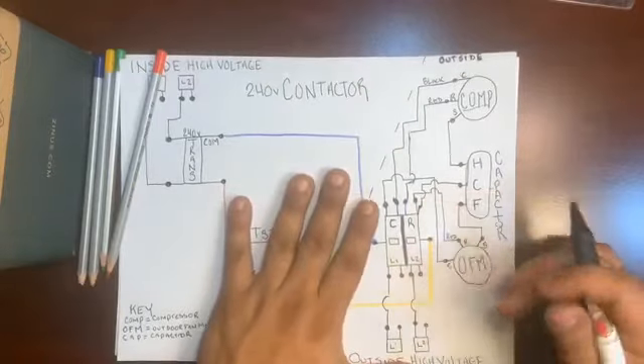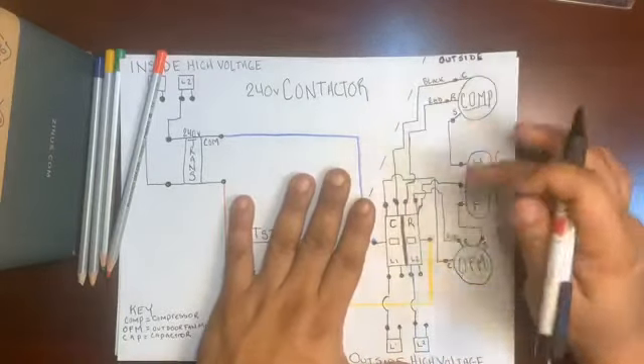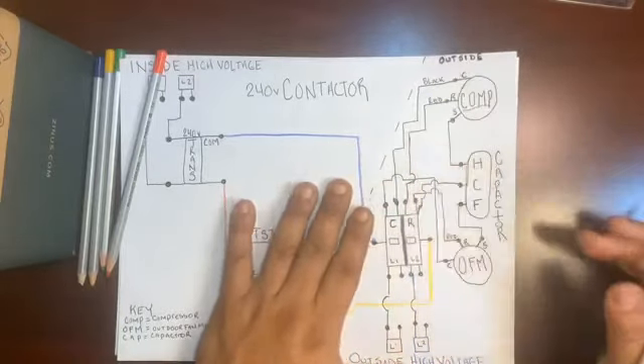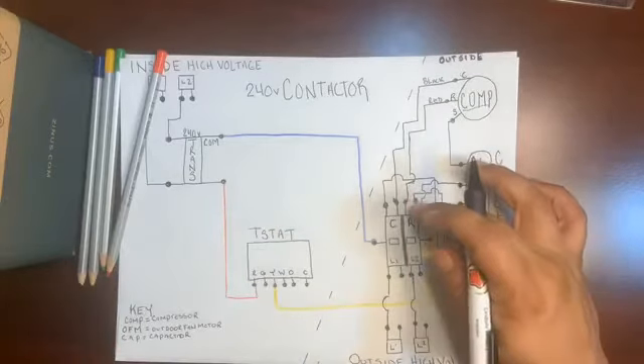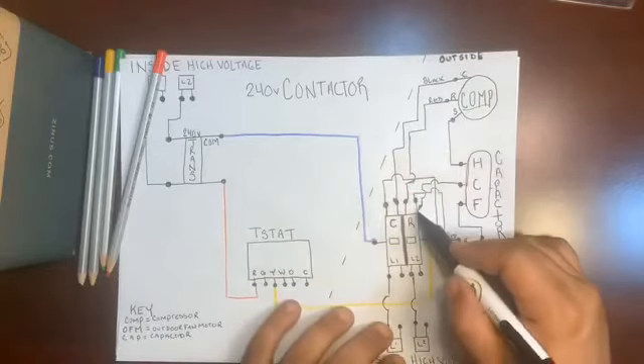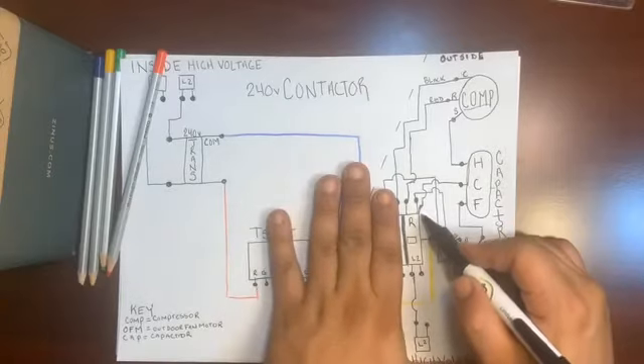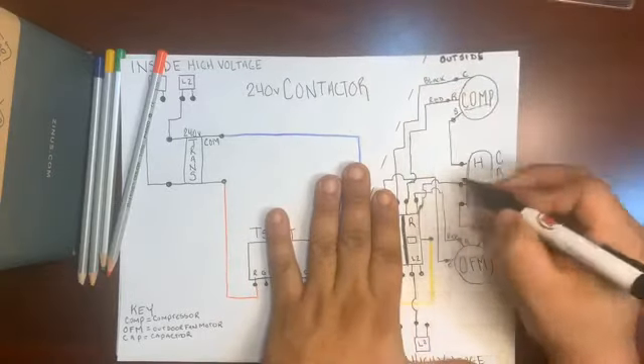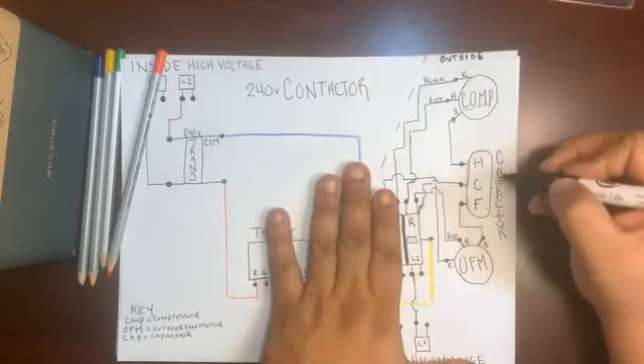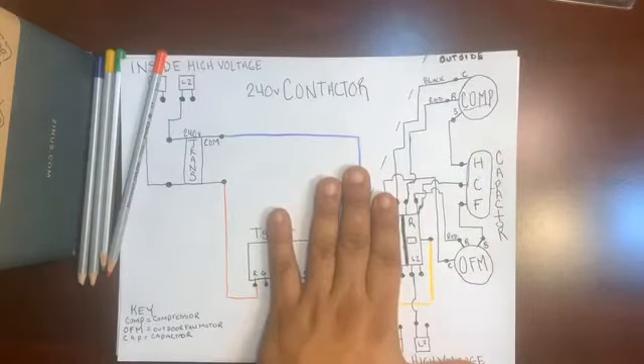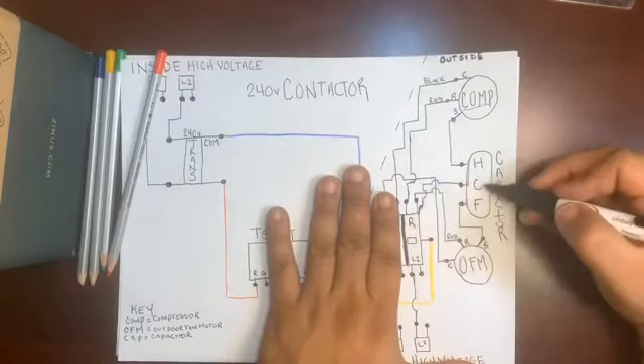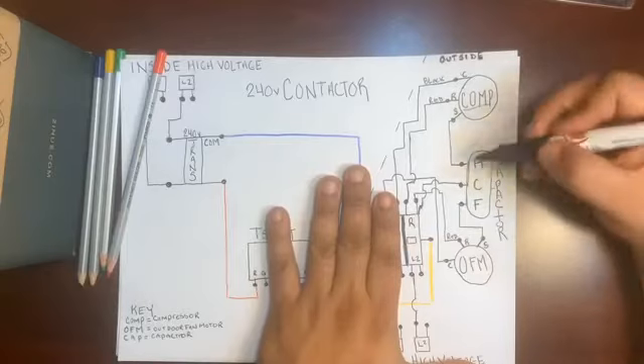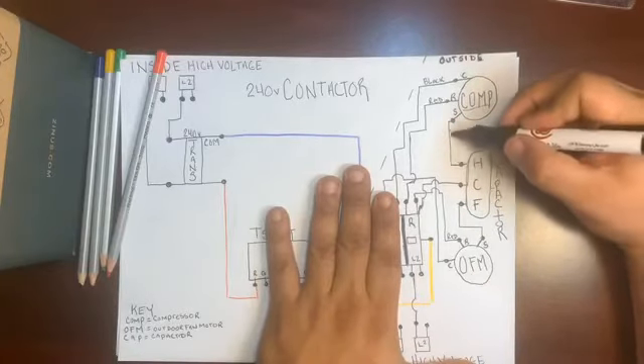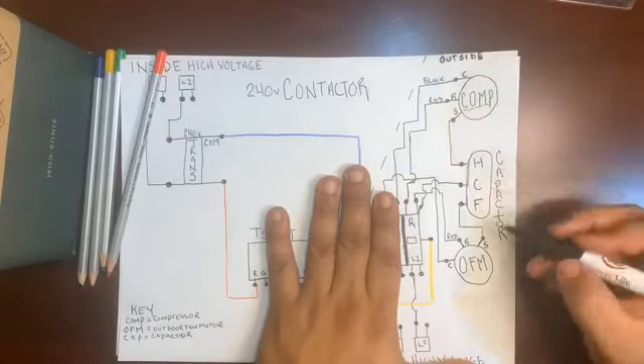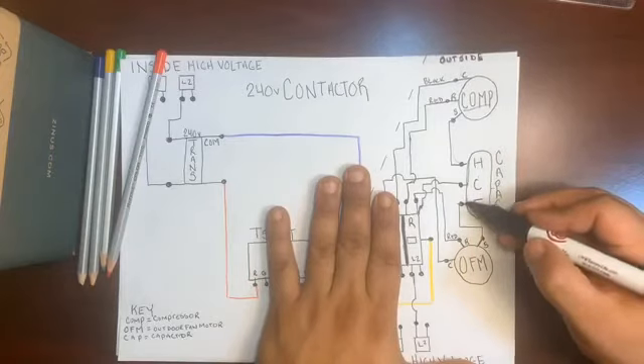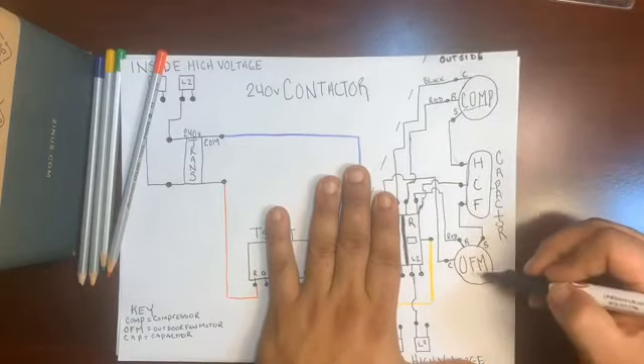When you pull a condenser off, you'll see a bundle of black wires here, and then a bundle of yellows or reds. And then one of these yellows or reds will leave the run side of the contactor, head over, and connect to the common side of the capacitor. So we have another leg of energy hitting the common side of this capacitor, and then we have one leg leaving hermetic going to the start winding on the compressor, and one leg leaving fan heading to the start winding on the outdoor fan motor.